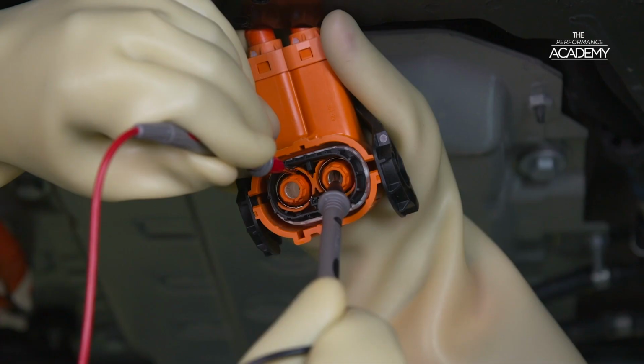In the film clip, you may have spotted that the test was done using the opposite probes to those given in the instructions. However, when carrying out any resistance testing, the polarity of the test probes has no effect on a resistance test. Both tests gave resistance values well above the 2 megaohms threshold value given, meaning the insulation is intact and not damaged. Now let's have a look at testing the resistance of just one main high voltage component.